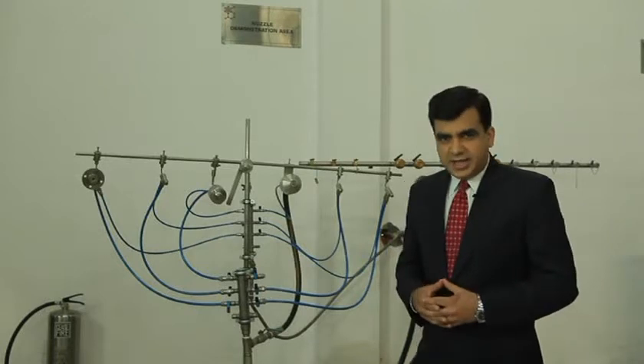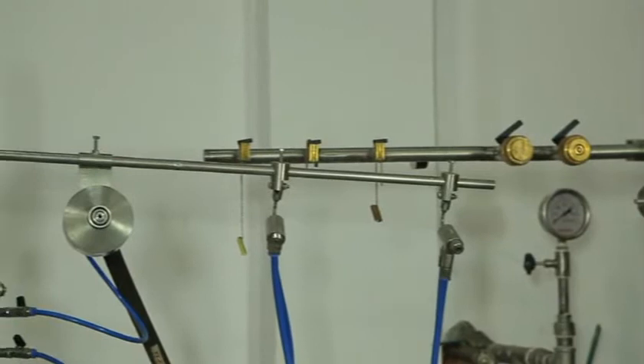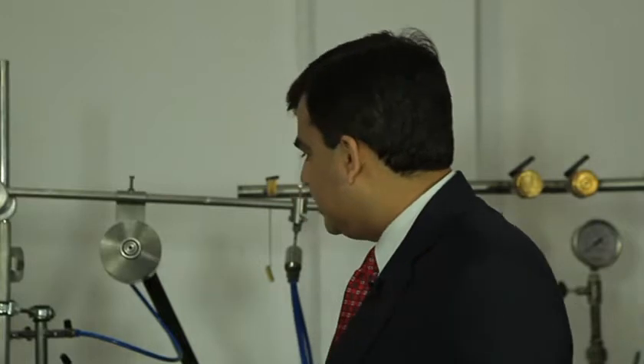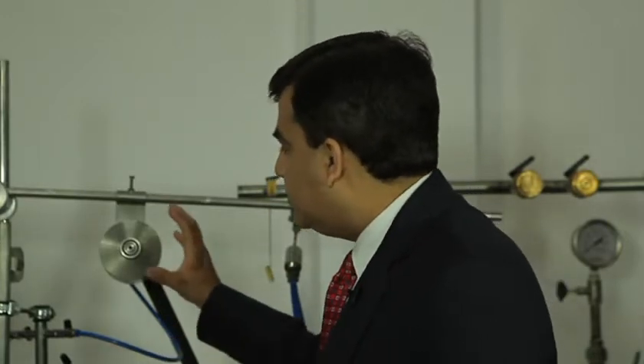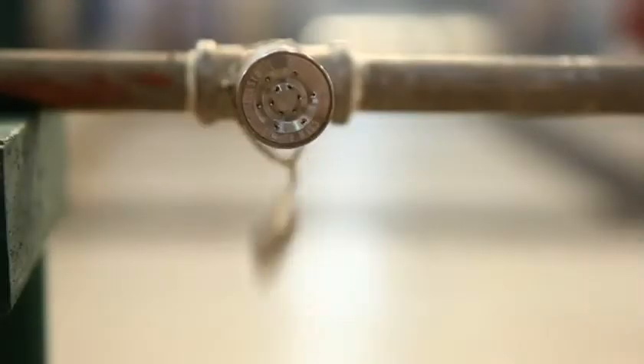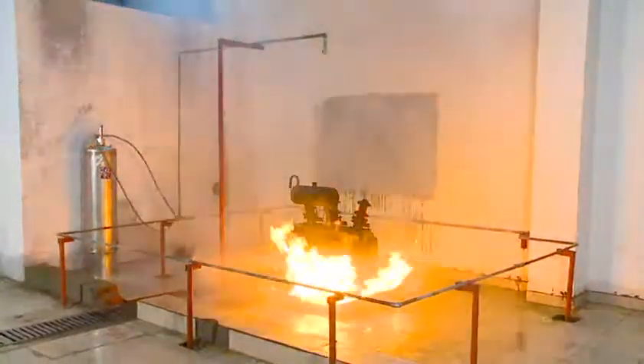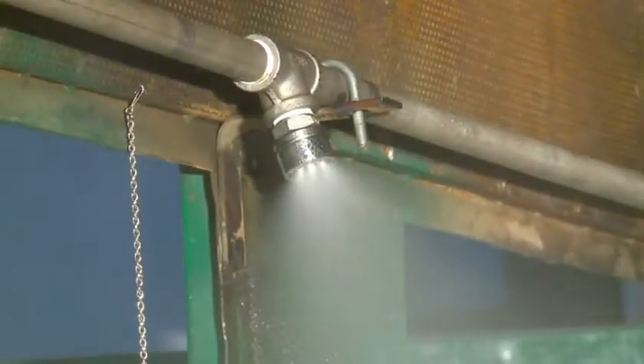Here's the nozzle demonstration area at the Ceasefire AI lab. There are special nozzles for single fluid systems. Twin fluid systems need separate pipes, one for nitrogen gas or compressed air, and the other for water. Both of these come together at the nozzle point and get converted into water mist. These nozzles have the capacity to break water down into a fine mist of as little as 40 microns, a revolutionary technology. 40 microns is really, really tiny. The mist is dispersed with great force. The microscopic particles travel much further than water because they're smaller and lighter than water particles.